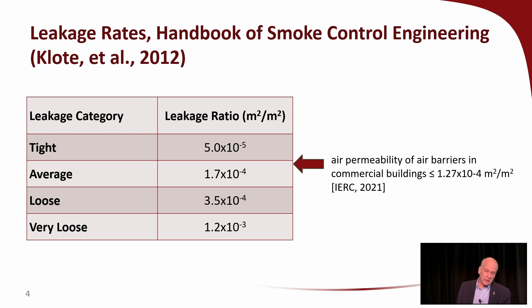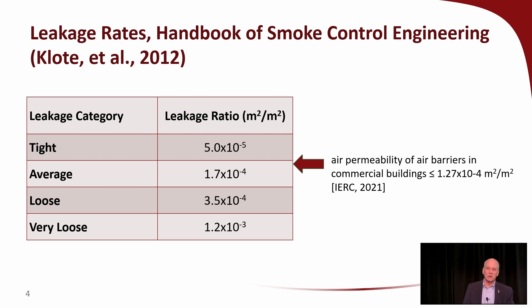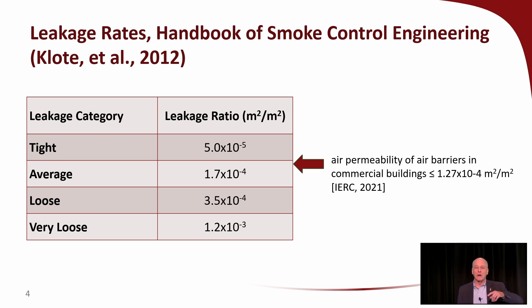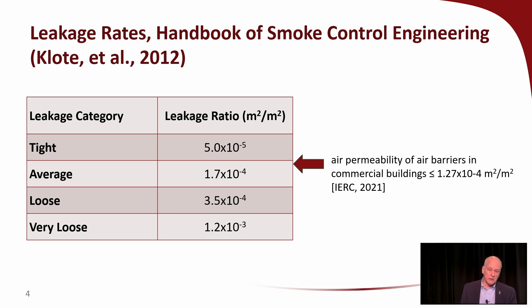There is some information from the International Energy Code 2021 edition that talks about the air permeability of air barriers — exterior walls in commercial buildings. They should be less than 1.27 × 10⁻⁴. So contemporary buildings where this code applies should be in the average range, a little less leaky than the average number in the table.